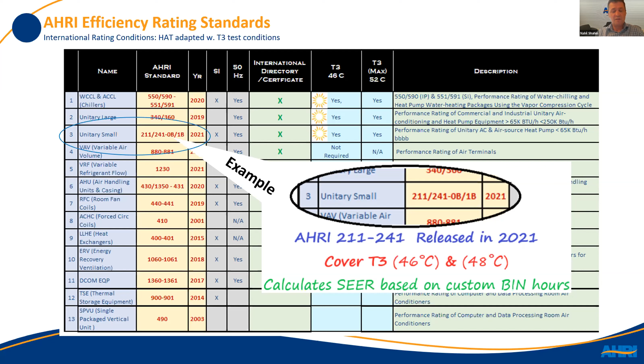Why AHRI certification in particular? For high ambient regions, when calculating seasonal energy efficiency, AHRI looks at a wider temperature range, covering 75% of the temperature range seen in the region, a typical high ambient area. Versus if you test per ISO, it only covers 30% as mandatory, which is most people only do mandatory testing.